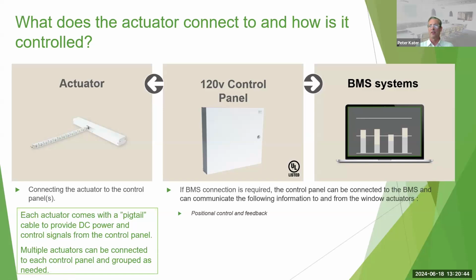The types of information communicated back and forth between the controller, the actuator, and the BMS include positional feedback and control signals. Operational speed that can be configured and monitored. Motor synchronization, which is where you have two or more motors on a vent that have to synchronize with each other, and an anti-entrapment function, which reverses the actuator briefly if it encounters an obstacle or a foreign object that gets trapped in the window.